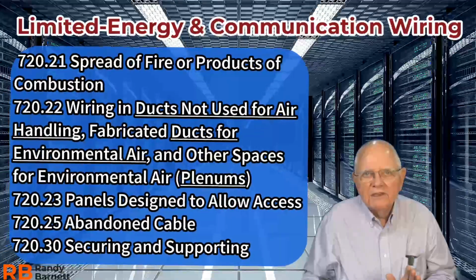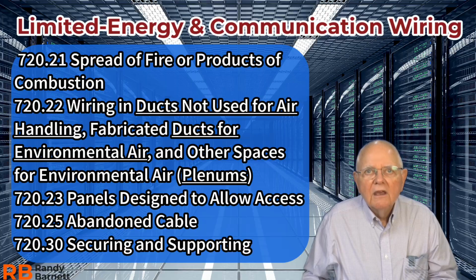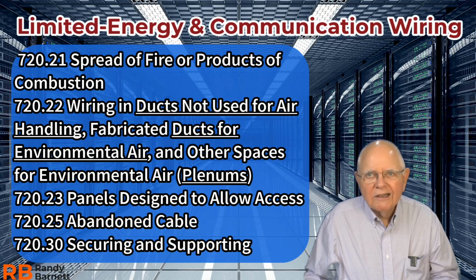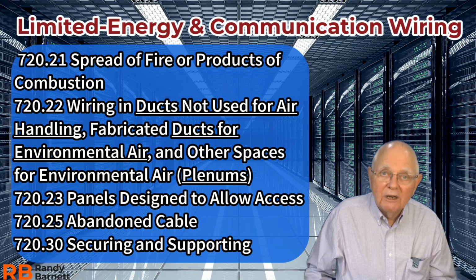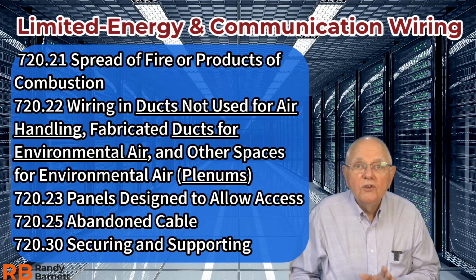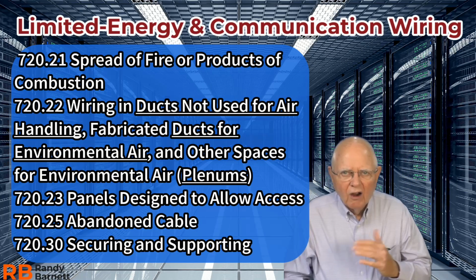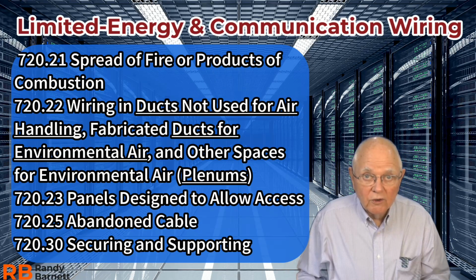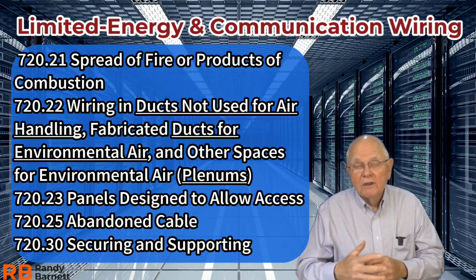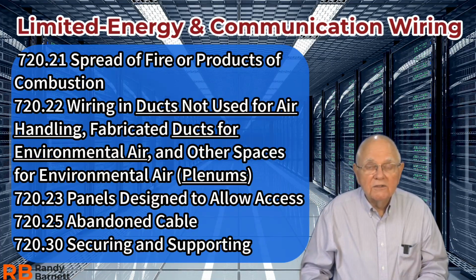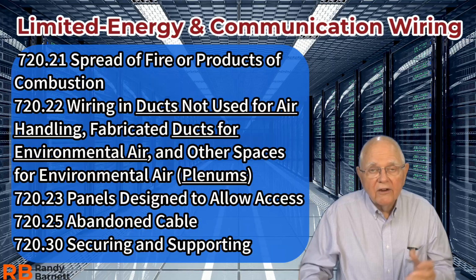Now, 720.21, always a big issue, fire stop, okay? Spread of fire, of products of combustion. We want to minimize that. So we have to use fire stopping or other approved methods in order to prevent the transfer of not only fire and flames, but products of combustion from one area into another.